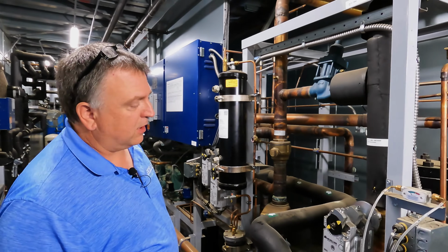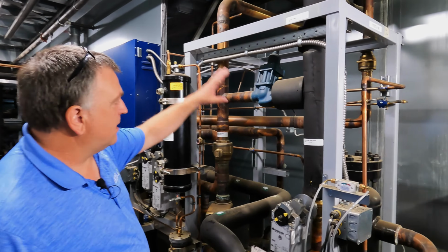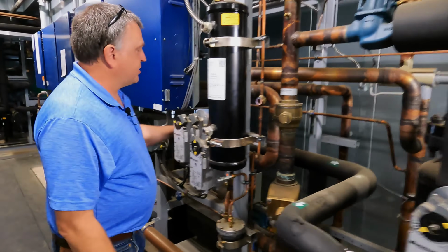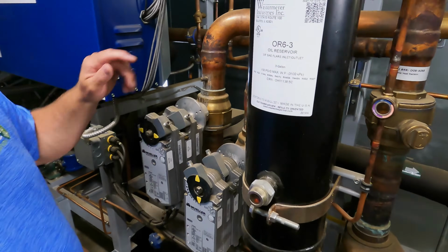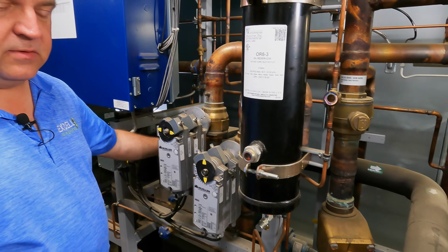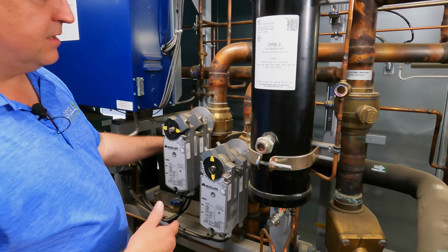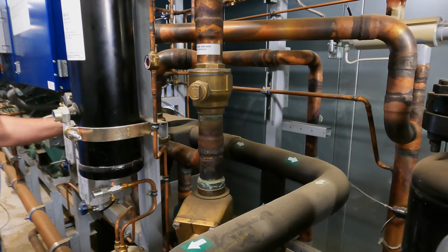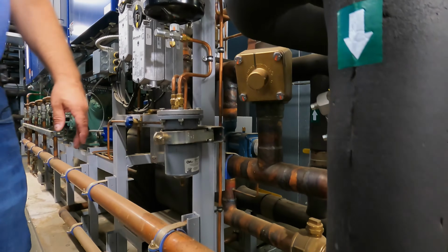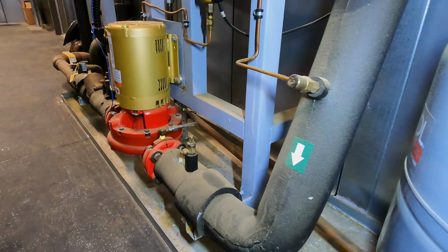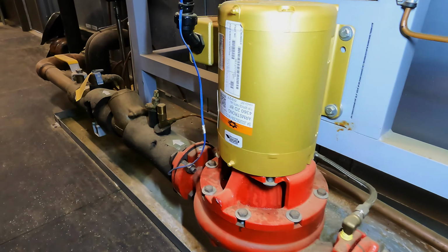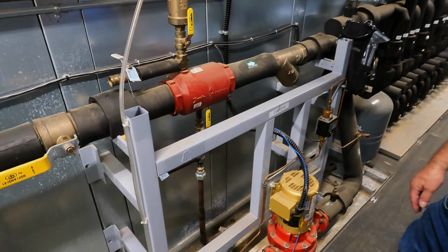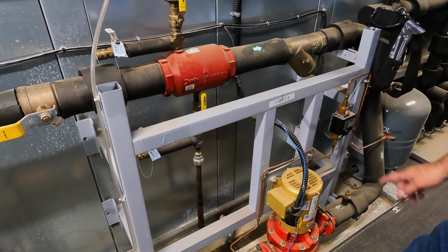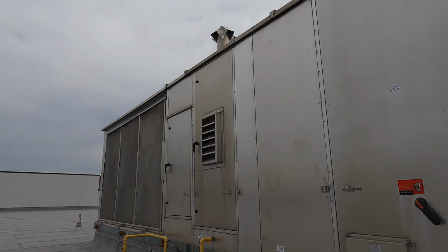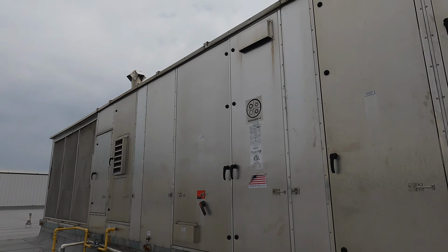Okay, as I was saying before about heat reclaim, as you can see all this tricky piping, we have a heat exchanger right here. Basically what happens is we have discharge gas coming off the compressors going into this heat exchanger. One side's refrigerant, the other side's glycol, and we're warming up that glycol. As we're warming up the glycol, we have a pump that's pumping glycol. It's hot glycol, probably 145, 120 degrees, depending on the conditions. That warm glycol is being pumped and circulated through a coil out in the main AC.